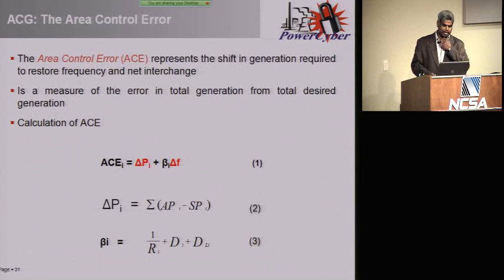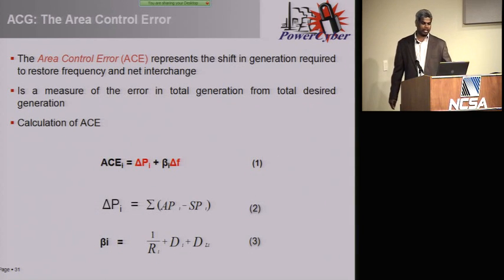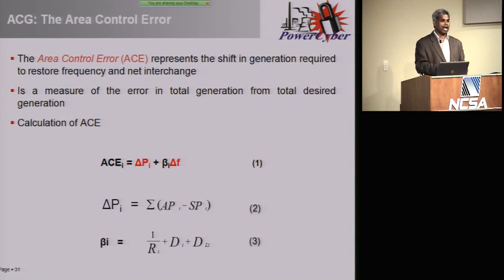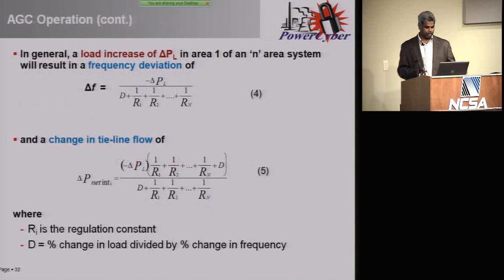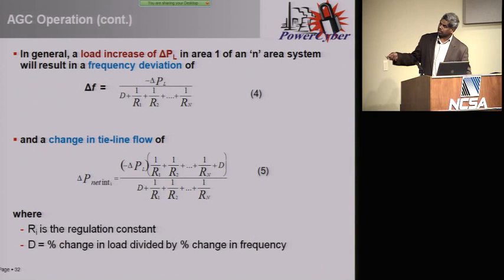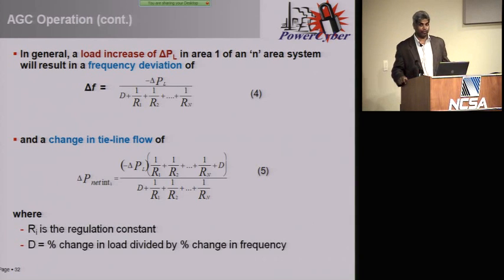Let's take an example. What is the area control error? It is the difference between the scheduled interchange and actual interchange between control areas. The actual interchange and scheduled interchange should be the same; in other words, the area control error should be zero. If it is above or below zero, positive or negative, generation has to be increased or decreased accordingly. The point here is that the tie line flow and frequency have to comply—that is very, very important.